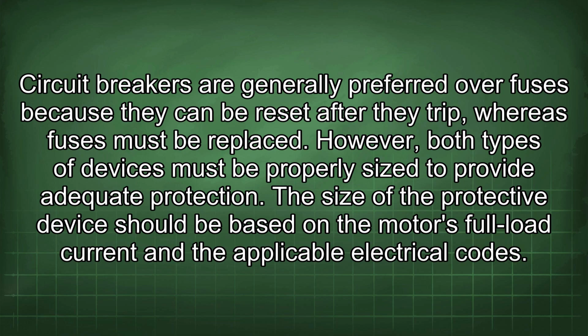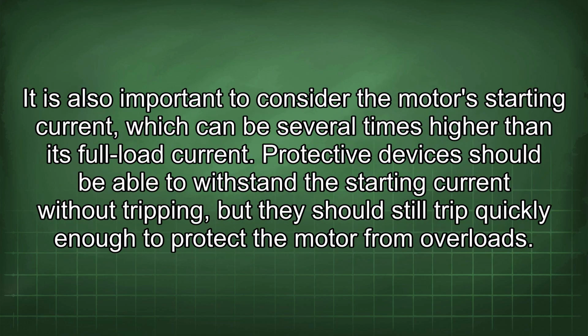The size of the protective device should be based on the motor's full load current and the applicable electrical codes. It is also important to consider the motor's starting current, which can be several times higher than its full load current. Protective devices should be able to withstand the starting current without tripping, but they should still trip quickly enough to protect the motor from overloads.